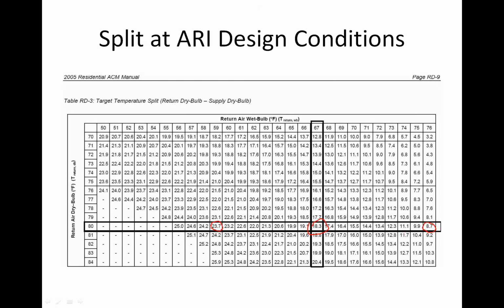That's why if you've ever started a system, when it's a new installation and the house hasn't had cooling before, and it's like 80 degrees outside and 80% relative humidity in the house, you'll start the thing up and it'll start running, and you're over there watching the thermostat. The thermostat's not coming down, but the house feels cooler, and you're going, what the heck? It feels cooler in here, but the thermostat's stuck at 80. And, of course, as any good service technician does, you justify in your head, oh, well, the walls are still hot, and that's why the temperature hasn't changed. Well, it has nothing to do with that.